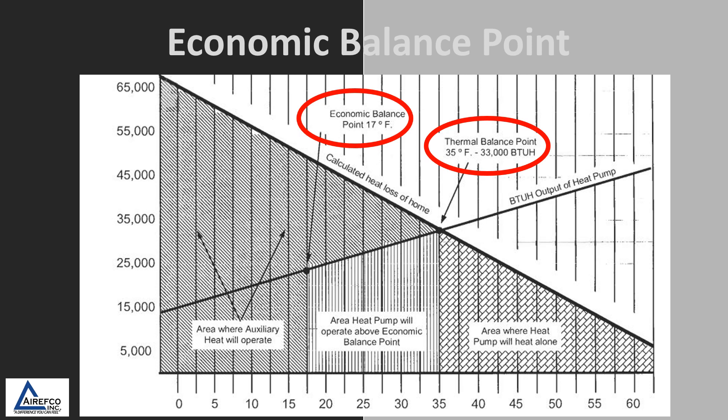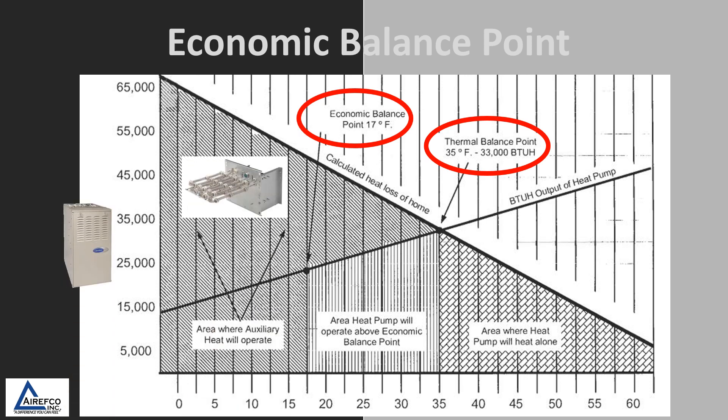This is the balance point where we switch from the operation of the heat pump to auxiliary heat. In most cases when we're talking about economic balance point, this would be a dual fuel application where operating the gas furnace would be more economical than operating the electric heat pump.